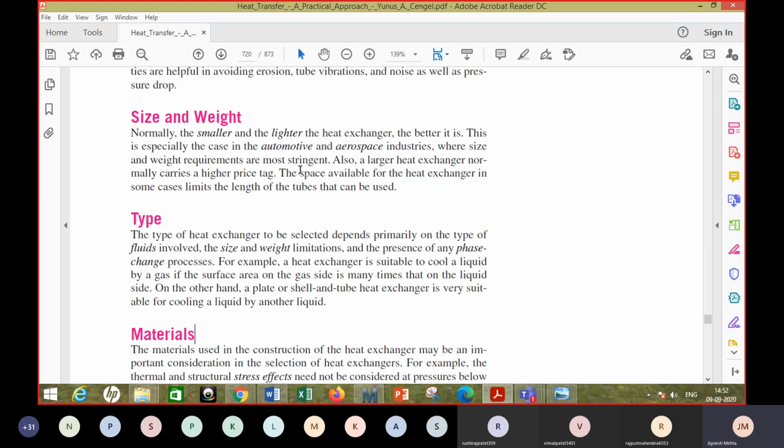But on the other hand, you see that the condenser of an air conditioner has air on one side outside the tubes, and the liquid with phase change flows through the tubes. The refrigerant flows through the tubes. So here you can increase the area on the outer side of the tube by putting many closely spaced fins, right? So there you can go for a fin tube heat exchanger, right?